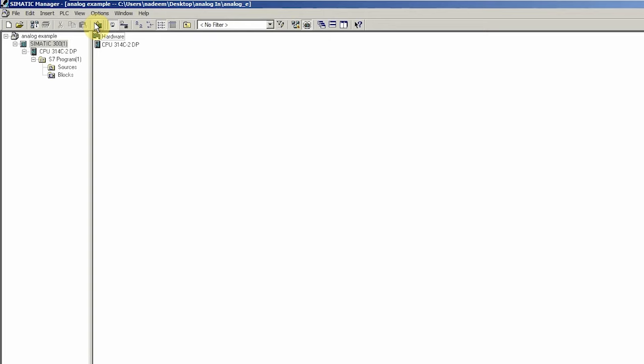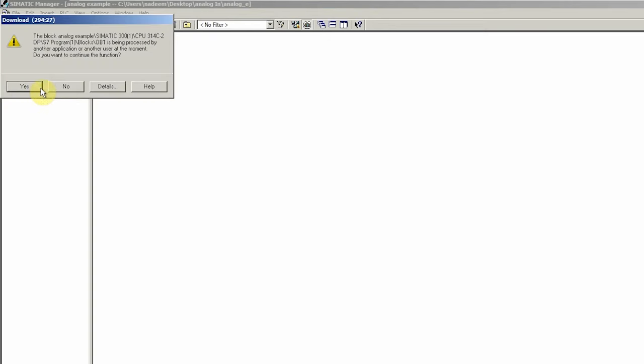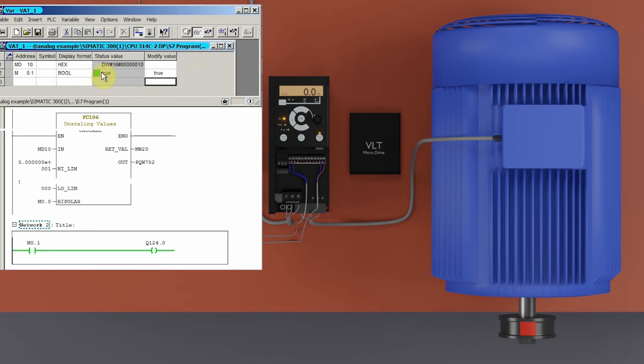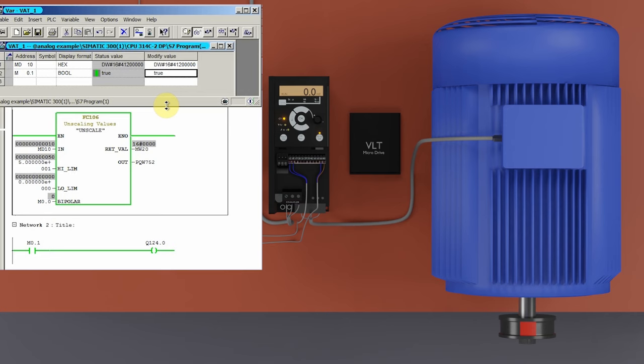Next we will download the project to the PLC and go online to monitor this function. Now if we turn on run command bit M0.1, it will turn on digital output Q124.0, the relay will turn on, and the VFD gets a run command signal. As you can see, the motor is still not running because the analog output signal is still set to 0 and VFD output frequency is 0. Now if we set the MD10 register value to 10 in the variable table, the VFD output frequency changes from 0 to 10 Hz and the motor starts to run at 10 Hz.